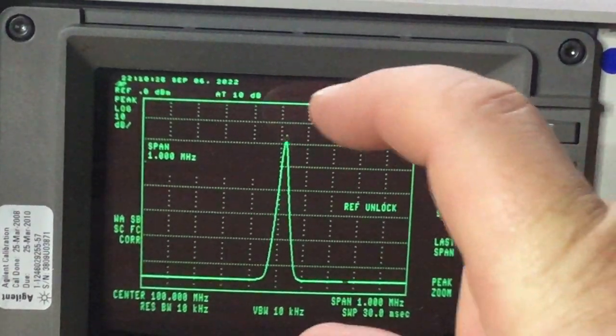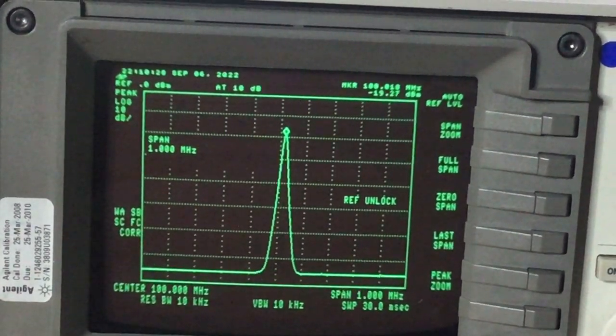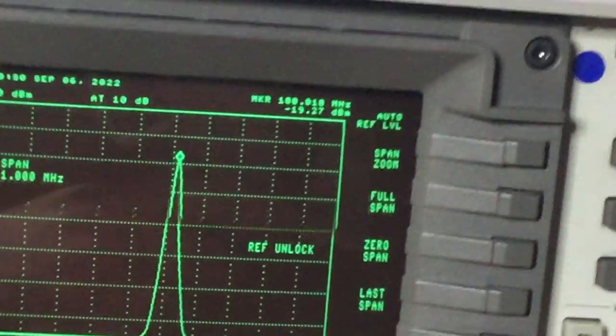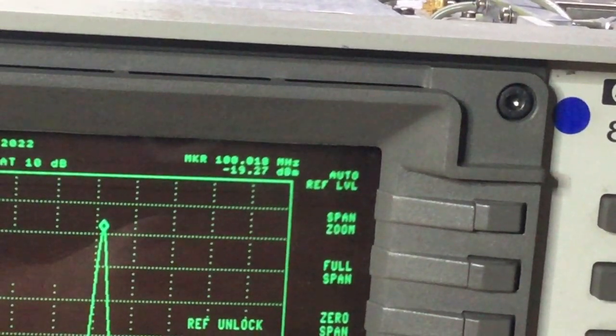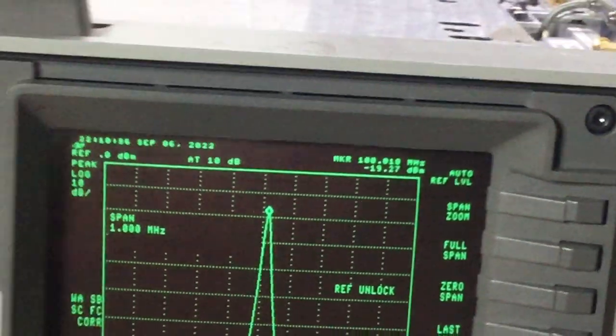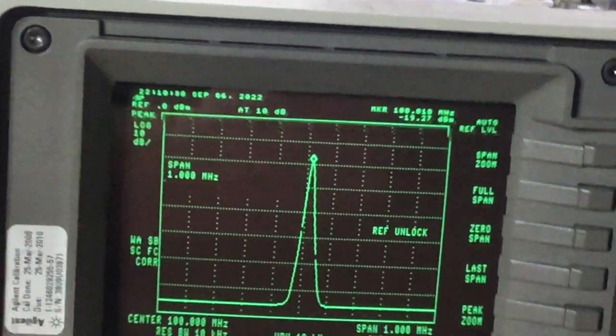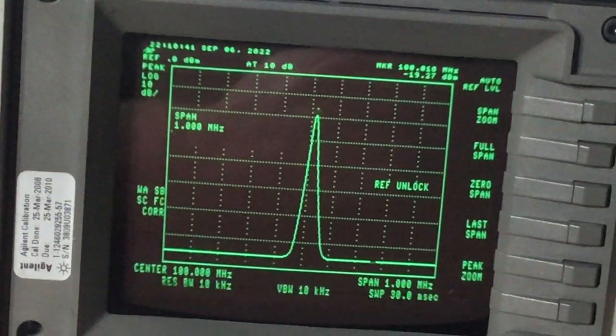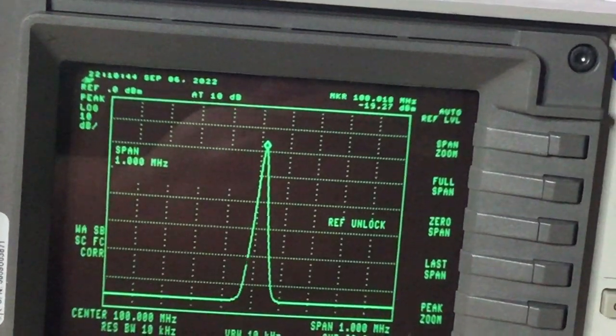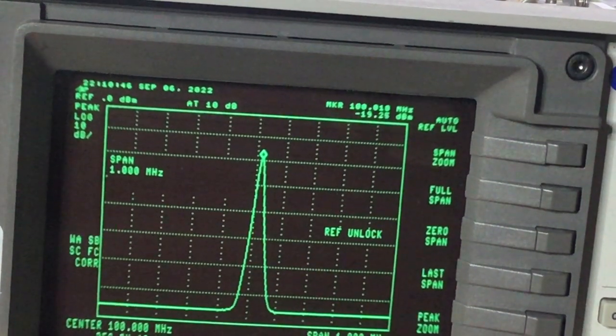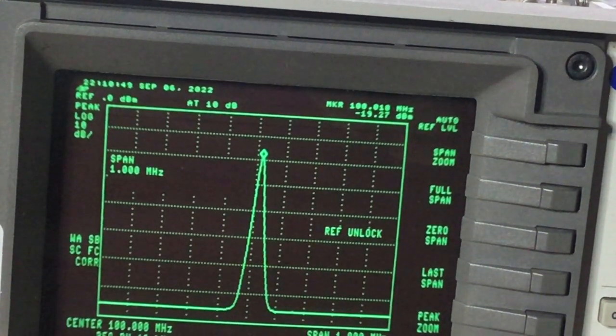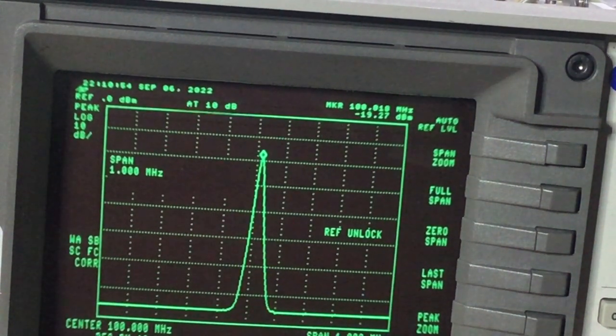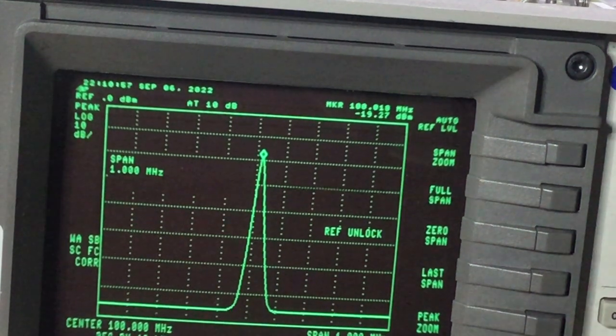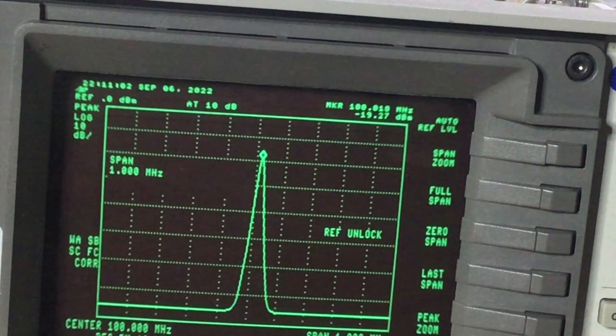Now the level itself is wrong because I'm measuring, if I can see that on the screen properly, -19.27 dBm when it's actually 0 dBm. Now it could be that I can calibrate that out. If we can actually get the frequency to remain stable and bang on frequency, we might be able to calibrate out that level error, because it uses a cal signal to calibrate the level as well as the frequency stability.